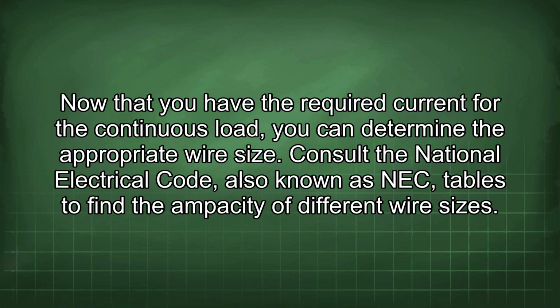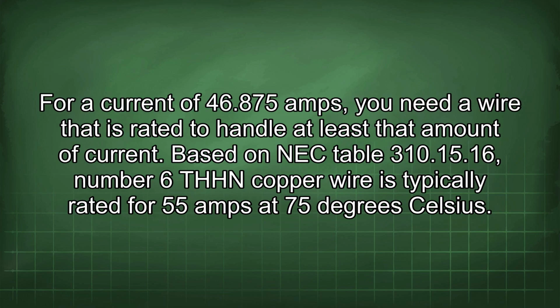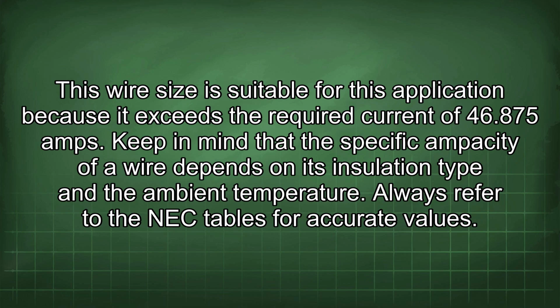Consult the National Electrical Code, also known as NEC tables, to find the ampacity of different wire sizes. For a current of 46.875 amps, you need a wire that is rated to handle at least that amount of current. Based on NEC table 310.15.16, number 6 THHN copper wire is typically rated for 55 amps at 75 degrees Celsius. This wire size is suitable for this application because it exceeds the required current of 46.875 amps. Keep in mind that the specific ampacity of a wire depends on its insulation type and the ambient temperature. Always refer to the NEC tables for accurate values.